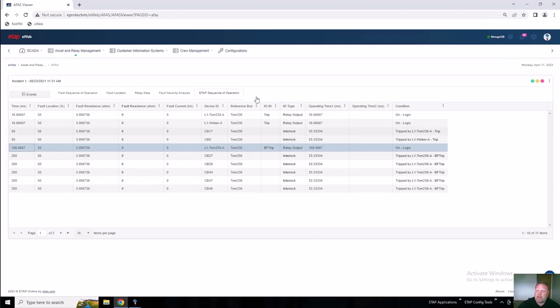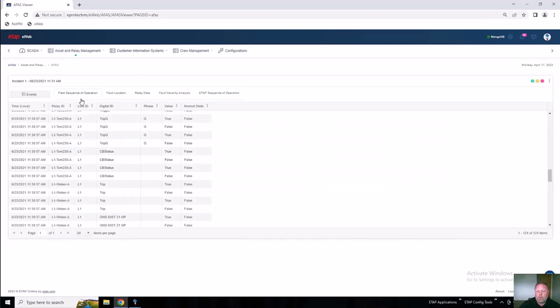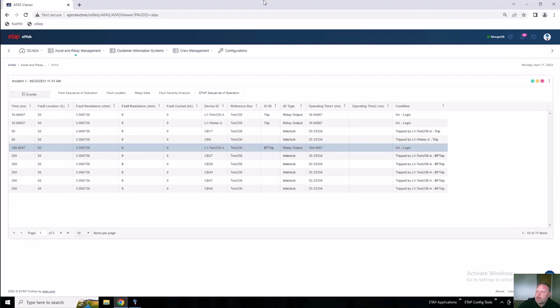you can compare that against the field sequence of operations, what is seen there, as well as what was seen in the SCADA. So we have our as found versus our as designed settings, and here you can validate the logic that has been put into the relays and the logic that is in the ETAP model, and make sure you have the most accurate ETAP model and that your protection settings in the field are correct. So this is, in general, my AFAS results. From here, you can generate reports which contain all of this information and more.